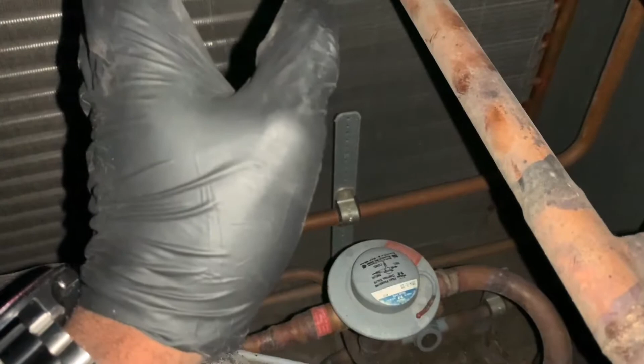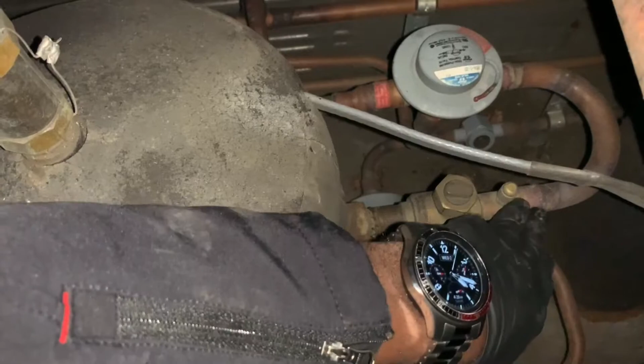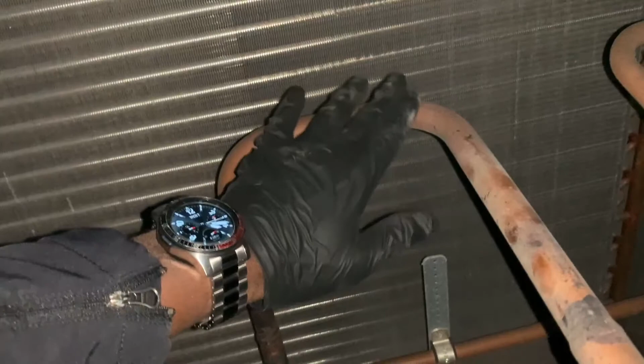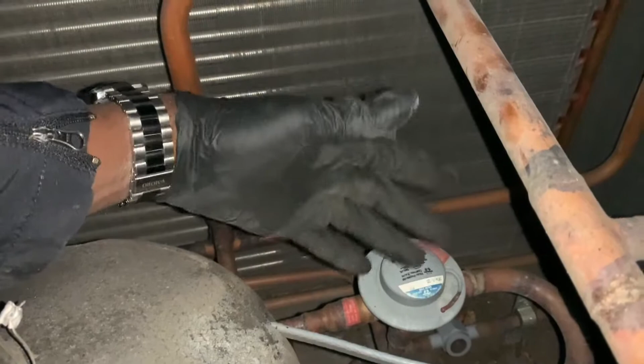And the discharge gas comes right over here to the liquid line, which is the receiver inlet, which is this liquid line that goes to the receiver inlet. And so the discharge gas bypasses through this valve right here while it's holding back the liquid refrigerant in the condenser. The valve is multiple action, and the discharge gas comes into the head of the top of the receiver, and the bottom of the receiver tank right here will have liquid refrigerant, and now that will push it through and force the liquid out into your liquid line. You have a liquid line on the bottom, there is a sight glass, and then to your metering device, whether it's TXV, LEV, EEV, whatever.